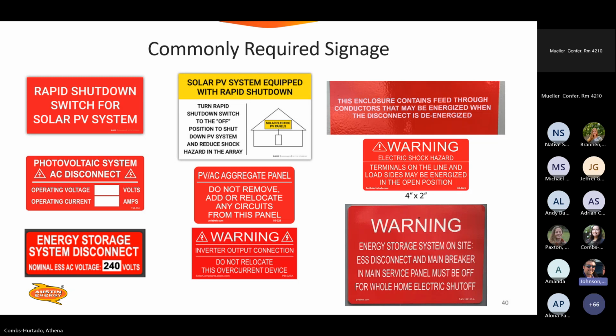This enclosure contains feed-through conductors that may be energized when this disconnect is de-energized. And ESS, energy storage systems, are one of the times where you can turn a disconnect off and both sides of it are still energized. If people are not aware of that, they can think, okay, cool, I shut the disconnect off, we're fine. I shut the breaker off, we're fine. And if they don't take a moment to test that voltage, they're going to be in for a very rude awakening when they realize both sides of it are still energized. And that leads us to: terminals on line and load may be energized in the open position, meaning the off position. It can still be on because when you turn that off, the batteries kick in. And then: energy storage system on site, ESS disconnect and main breaker in main service panel must be off for whole home electric shutoff. Next slide.